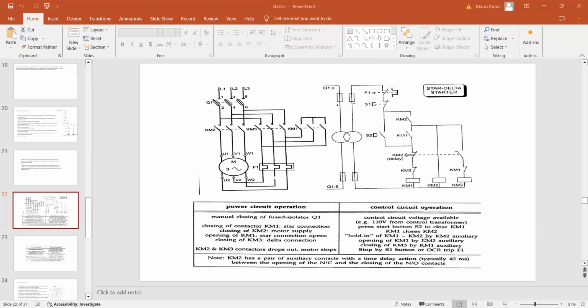Opening of KM1 by KM2. So the contact of KM1 opens by KM2. How by KM2? Because there is a time delay. As soon as KM2 gets energized, this will open after 40 milliseconds. Closing of KM3 by KM1. KM3 is getting closed by KM1 because this is going to open and this is going to close, right? Yes, sir. And stopping you can do by disconnecting using S1. Understood? Yes, sir.